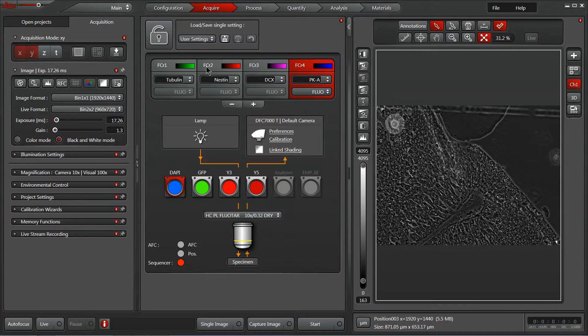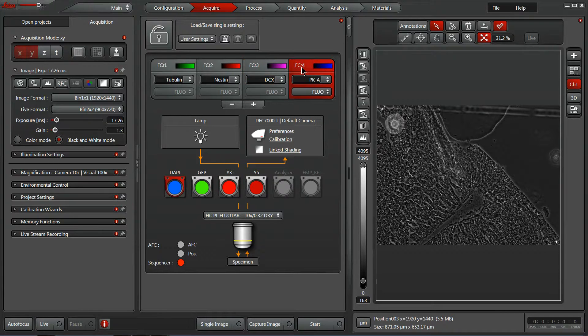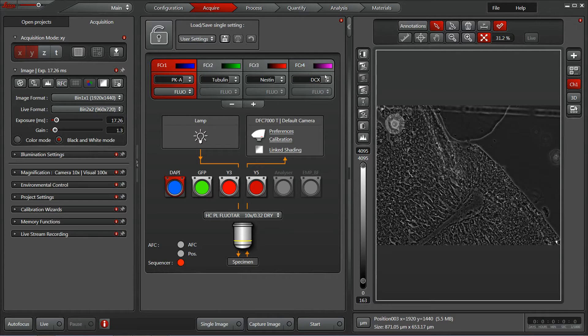Each of these channels can be customized with different exposure times and illumination settings. If you prefer to do your DAPI first, you can simply select that cube, click on it, drag it to the position you'd like, and it'll reassign the order while keeping all the information consistent. I always prefer to do DAPI last, however, since the UV light used to excite DAPI can also excite other fluorophores, photoconvert fluorophores, or aid in bleaching of fluorophores. So we were always taught in my lab to image DAPI last.